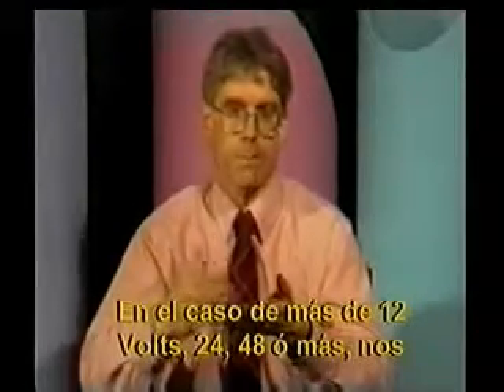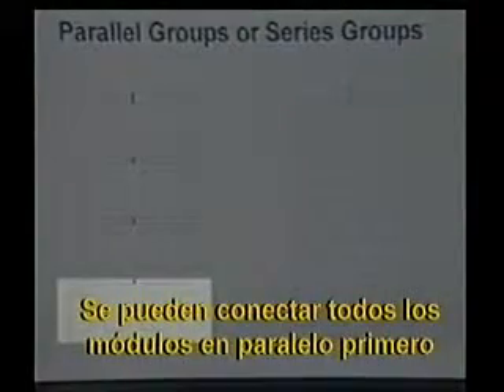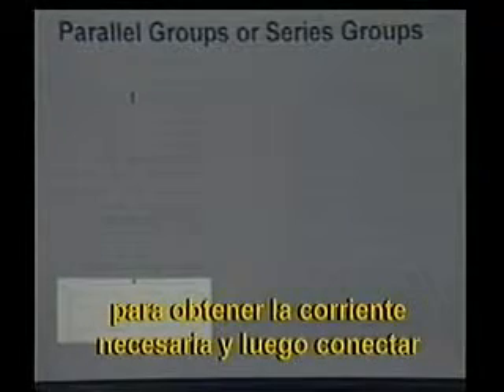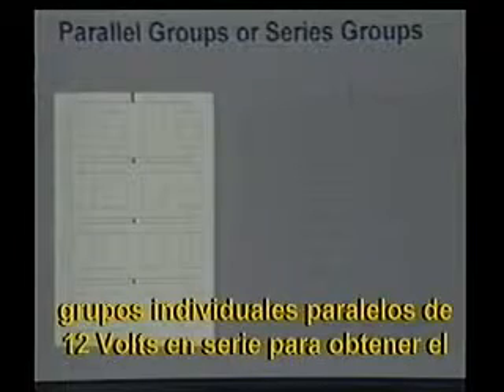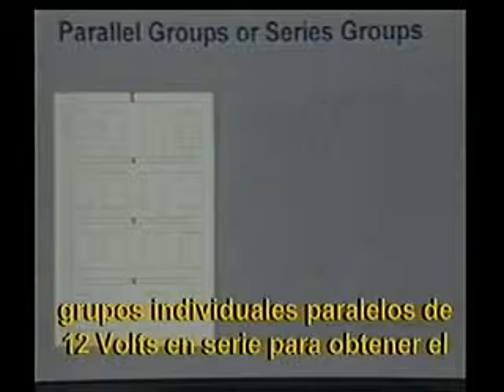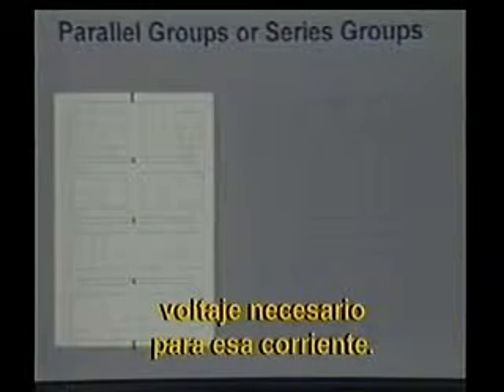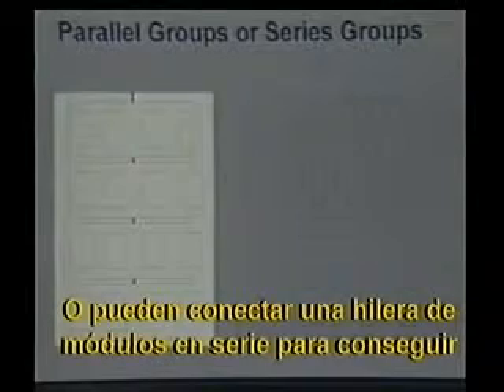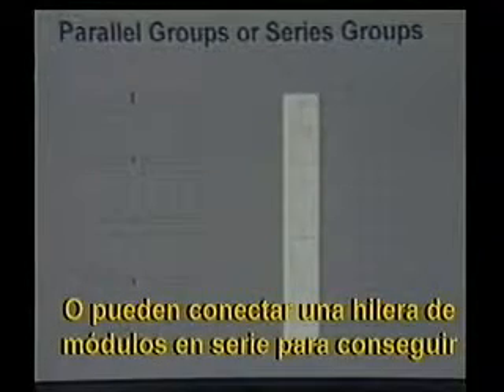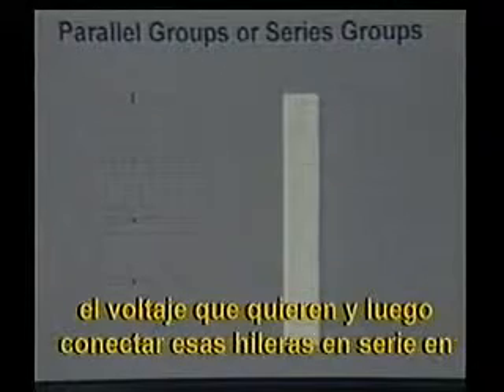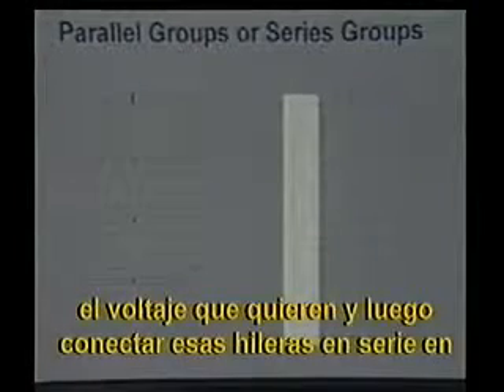In the case of anything greater than 12 volts, 24 volts, 48 volts or greater, we're faced with basically two choices. You could either wire all of your modules together in parallel first to give you the current that you need, and then connect individual 12-volt parallel groups in series to give you the voltage that you need for that current. Or you could connect a string of modules together in series to achieve the voltage that you need, and then connect those series strings together in parallel to give you the current that you need.